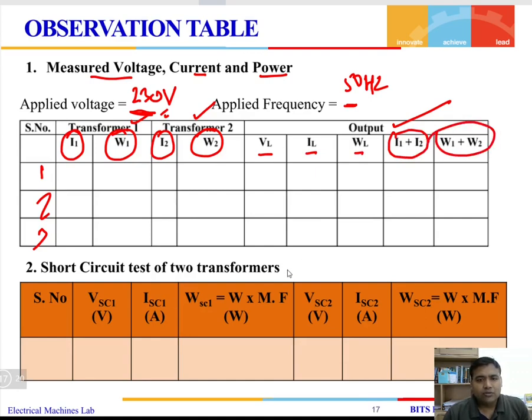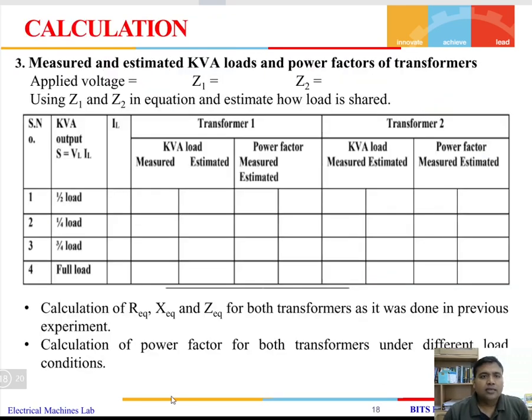And then we perform the short circuit test for the two transformers. What is the short circuit voltage, short circuit current, and short circuit power? This we are going to measure for transformer 1 and transformer 2. This part is for transformer 2, this part is for transformer 1. Then we do the calculation now.